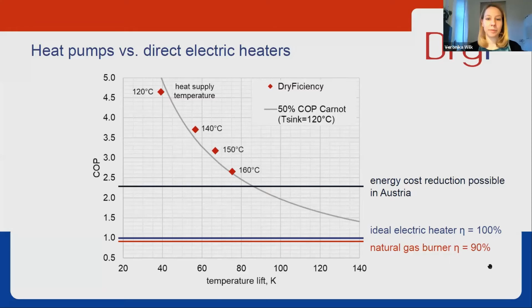As long as the COP is above those two lines, there are energy savings compared to these two technologies. So it's still possible to move to higher heat supply temperatures while saving energy compared to a direct electric heater or compared to a natural gas burner.